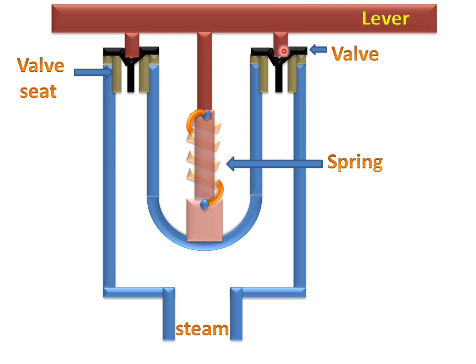The lever will regain its position and the spring will regain its position. So at this time, the valve will be closed. And when steam enters and creates pressure in the section, then this valve will open. So this is the working of the spring loaded safety valve.